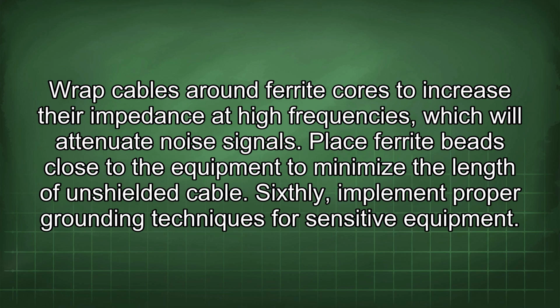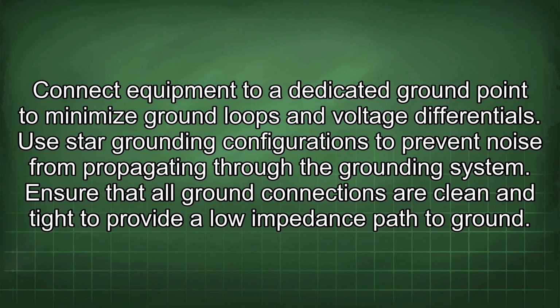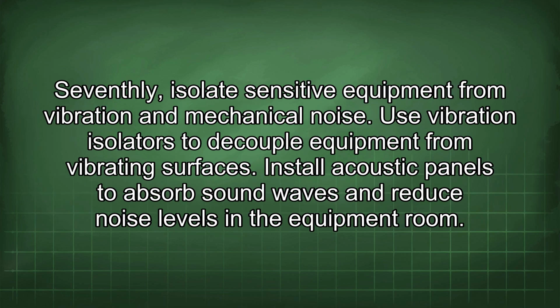Sixthly, implement proper grounding techniques for sensitive equipment. Connect equipment to a dedicated ground point to minimize ground loops and voltage differentials. Use star grounding configurations to prevent noise from propagating through the grounding system. Ensure that all ground connections are clean and tight to provide a low impedance path to ground. Seventhly, isolate sensitive equipment from vibration and mechanical noise. Use vibration isolators to decouple equipment from vibrating surfaces. Install acoustic panels to absorb sound waves and reduce noise levels in the equipment room.